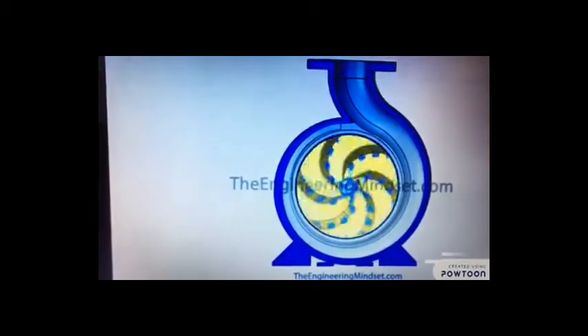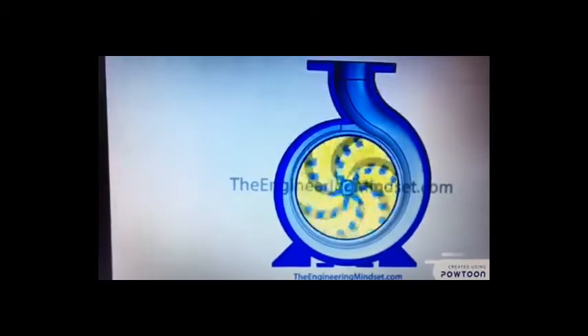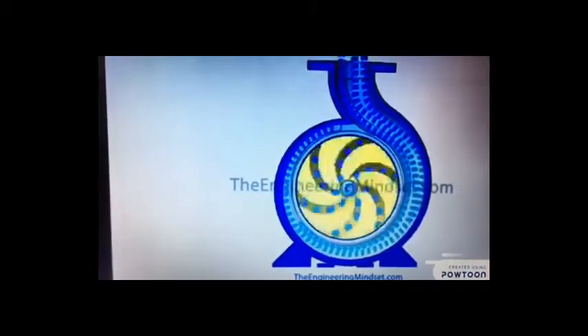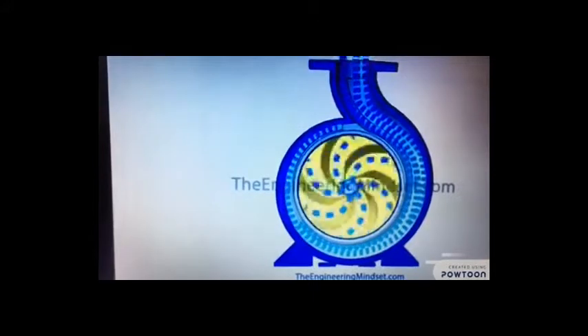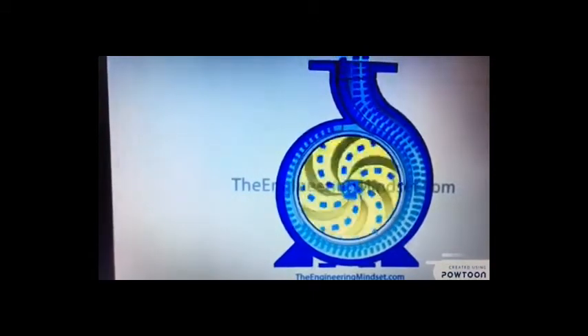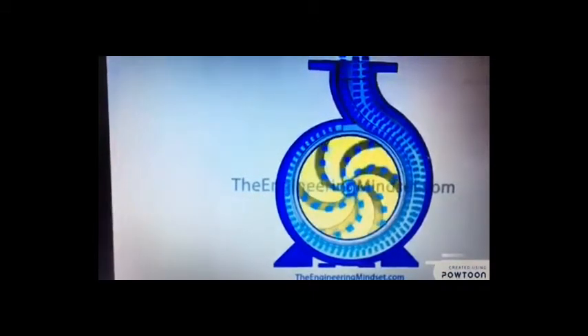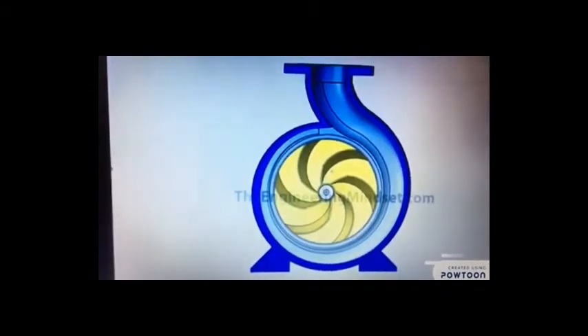As the water enters the impeller, the force pushes it out toward the edge. All the water that has been pushed against the edge is collected in the volute. All that has collected makes its way out to the top. The impeller has a curved vane shape. This type of impeller is known as a backward curve type of impeller. The vanes do not push the water out. The water flows between the vanes and the vanes provide force that pushes the water out of the pump.